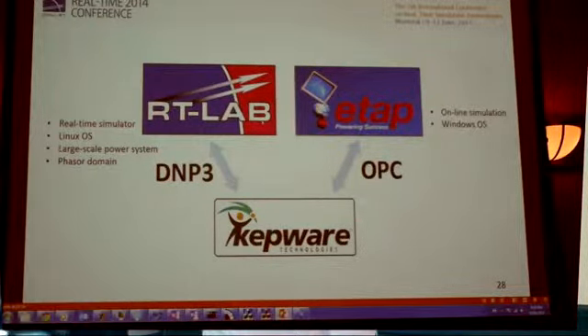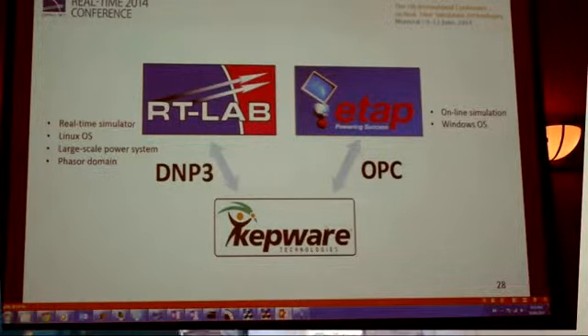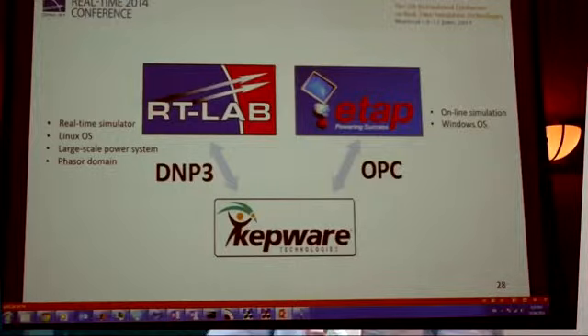To communicate between RT Lab and ETAP, we are using Kepware as the OPC server, because the RT Lab model is running on a Linux machine and ETAP is running on Windows. From RT Lab to Kepware we use DNP3, and between Kepware and ETAP we use OPC.